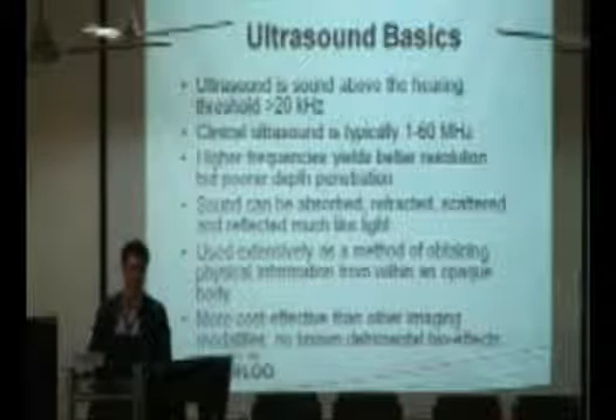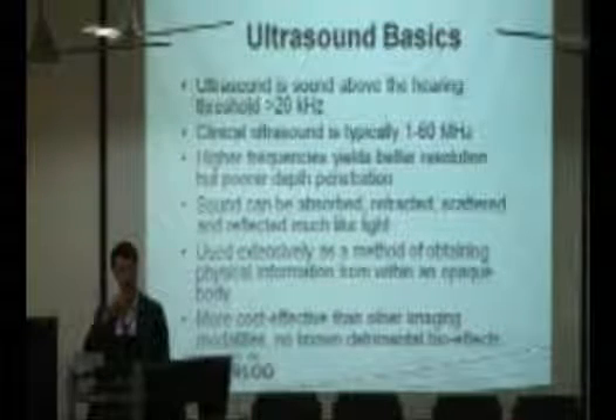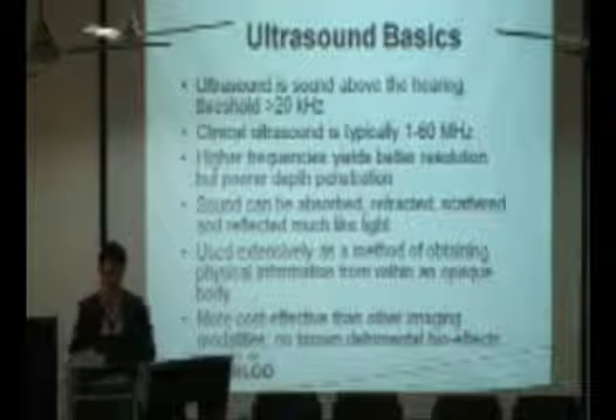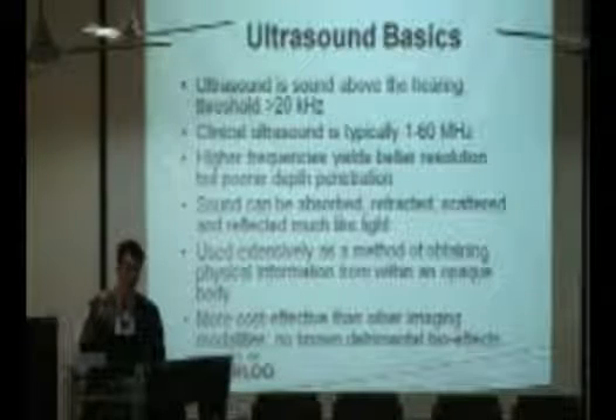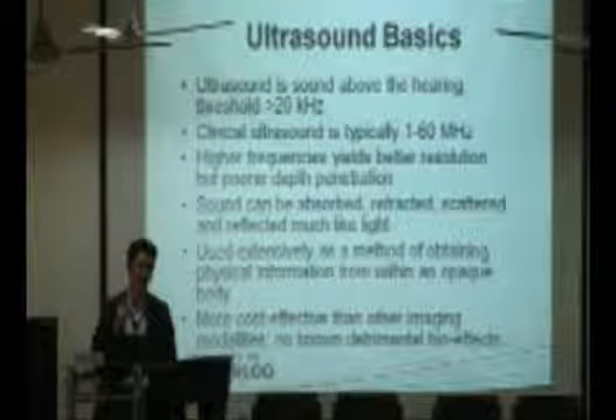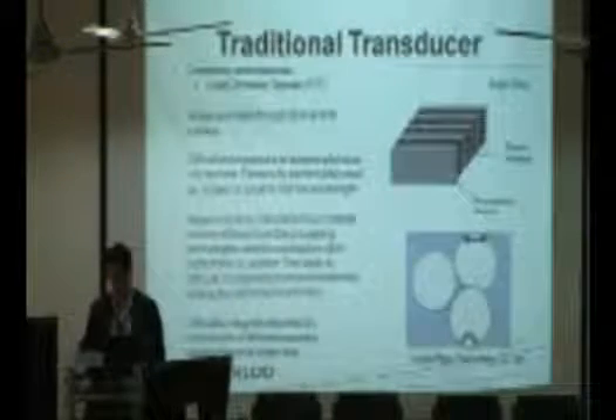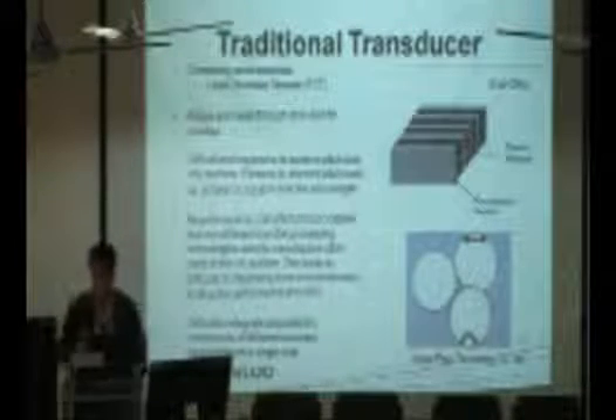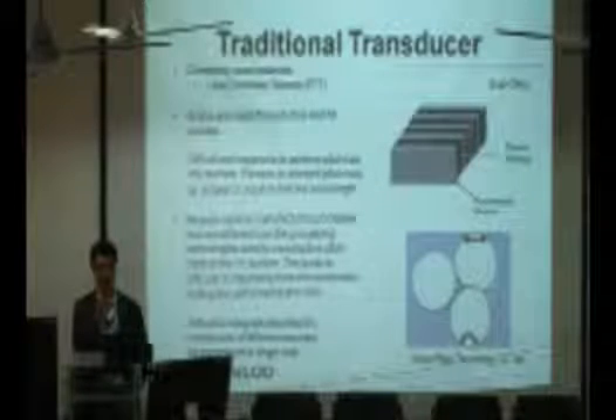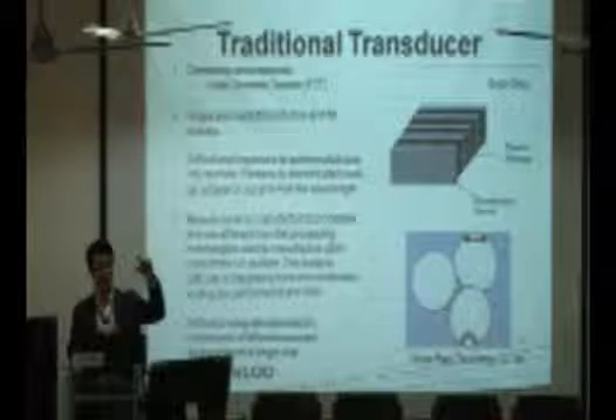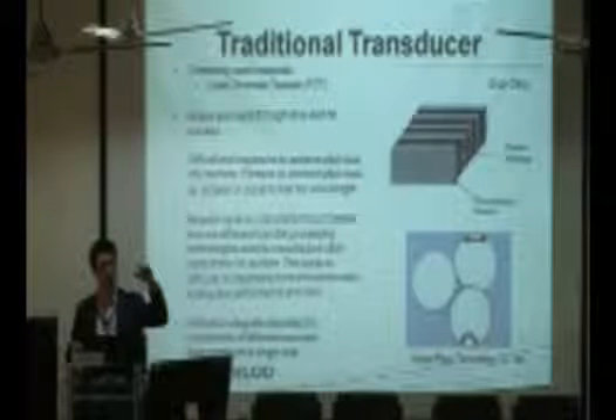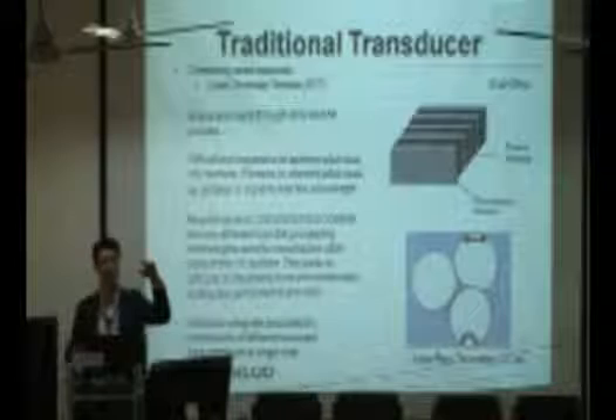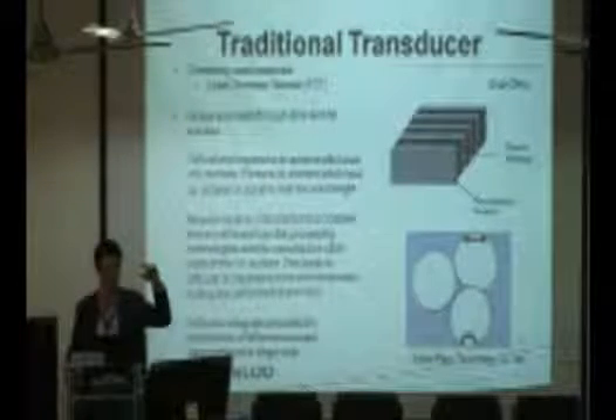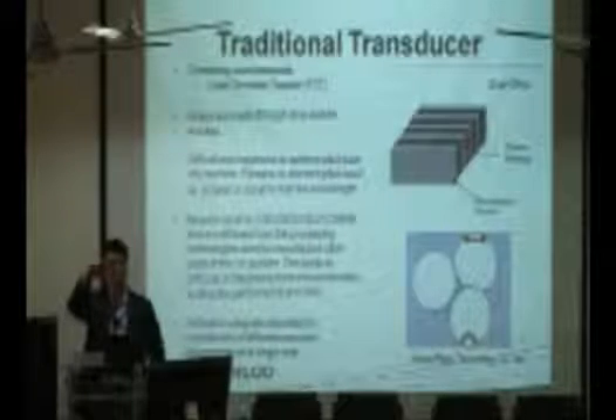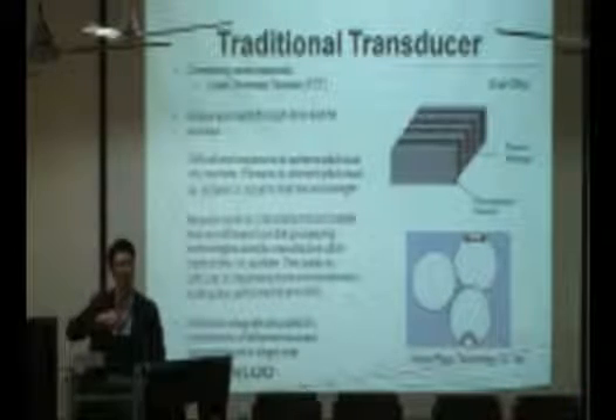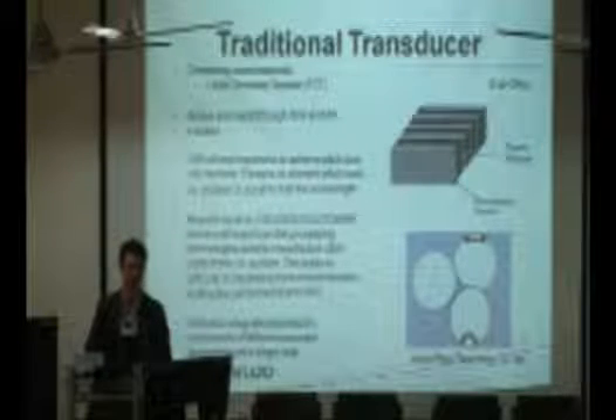Now, if we want to move beyond the 60 megahertz regime, the current way of generating ultrasound does not meet that requirement. In the future, if we are looking at sub-micron structures within tissue with ultrasound, it simply cannot be achieved by the conventional way of generating ultrasound. The conventional way is this. We have a piezoelectric material. We apply voltage to this material, and it would obviously deform. We take away that voltage, and the material would move back to its original shape. By applying and taking away voltage, we are making the piezoelectric material vibrate. The speed of the vibration determines the frequency of ultrasound we can generate from that piezoelectric material.